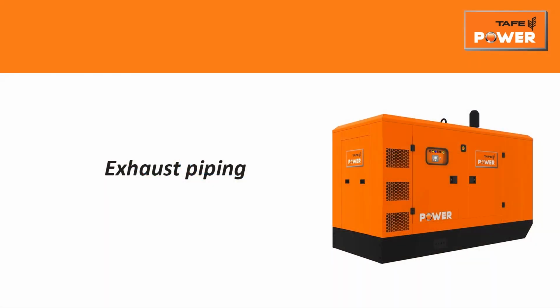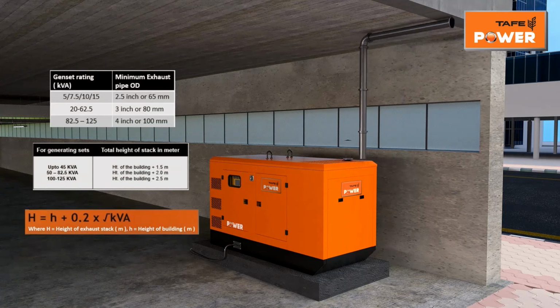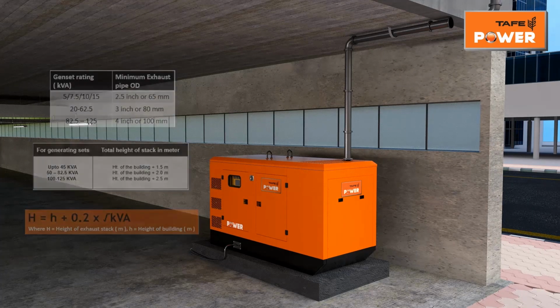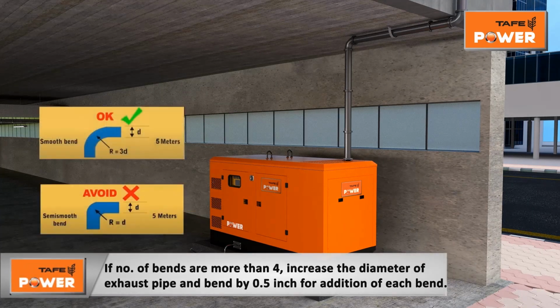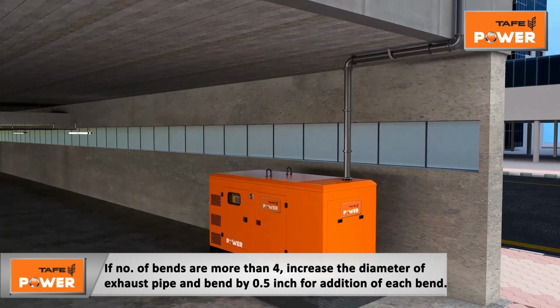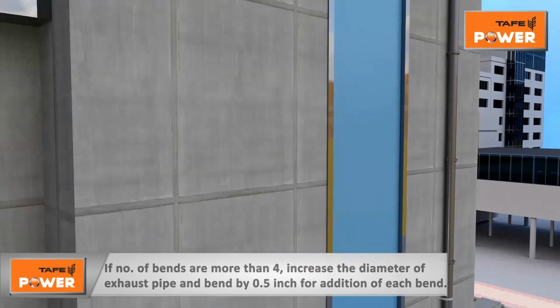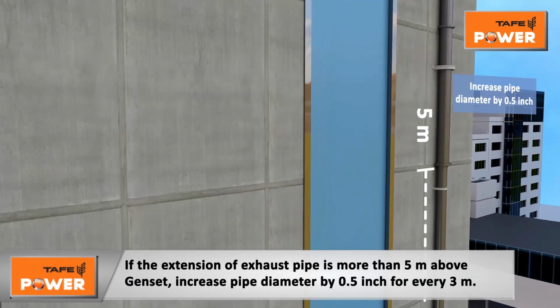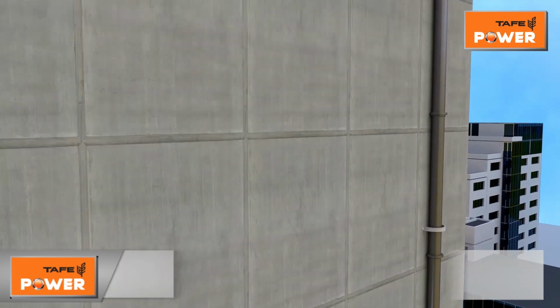Exhaust piping. If exhaust piping extension is required, then it is to be done with support and clamping. Extend the exhaust piping using proper flange and maintain extended exhaust pipe diameter and height as per TAFE power guidelines. If the number of bends are more than 4, increase the diameter of exhaust pipe and bend by 0.5 inches for addition of each bend. If the extension of exhaust pipe is more than 5 meters above genset, increase the pipe diameter by 0.5 inch for every 3 meters.